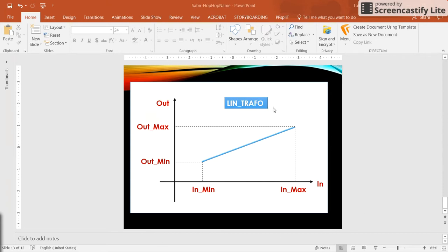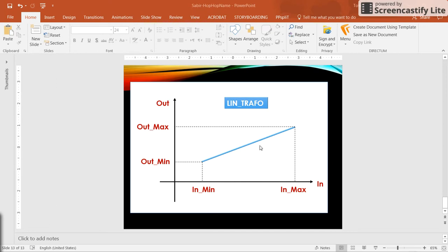The linear transformation function block behaves in this way: it takes an input variable and creates an output variable accordingly. We have four parameters: the minimum value for input, maximum value for input, minimum value for output, and maximum value for output. Providing a value in the input range between minimum and maximum, we get a corresponding output value between the minimum and maximum of the output. This is a linear transformation — whatever we have in the input is transformed to some other range in the output variable.